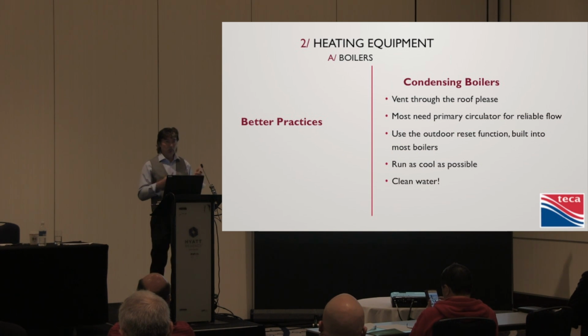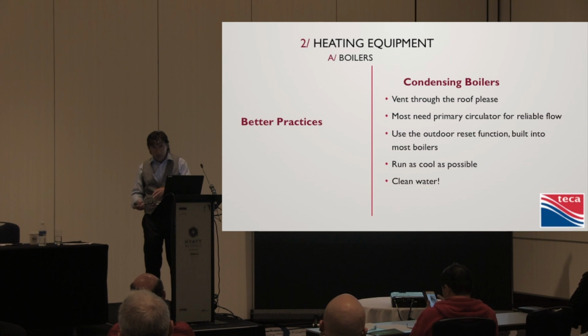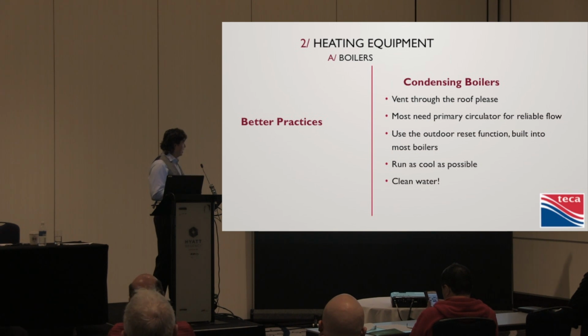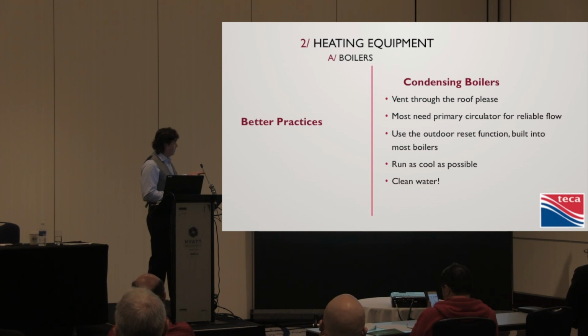If you retrofit a building and it's all baseboards and you just crank that thing to 180, you do not have a condensing boiler. You do not have a 90% efficient boiler. You've got a standard boiler that's running about 85% efficiency. Kind of a waste of time. The only thing you do have there is the load matching, though. So run it as cool as you can. So address the loads accordingly.